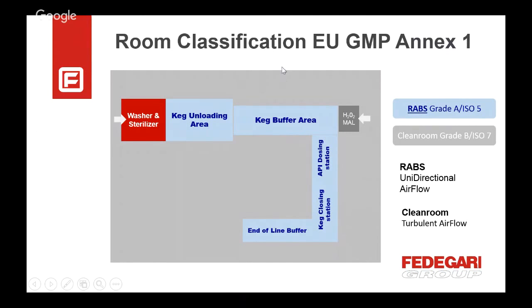Here you have a feeling of the classification according to the European GMP, as the customer is European, but it doesn't make a big difference also for US FDA. So we have the clean room, that is the background environment, in a grade B or ISO 7 environment, while the RABS is in a grade A or ISO 5 environment. Within the RABS, we have designed a unidirectional airflow to provide the best protection of the critical points. The clean room is designed with turbulent airflow. We have almost 30% coverage with HEPA filters held by the ceiling of the clean room.